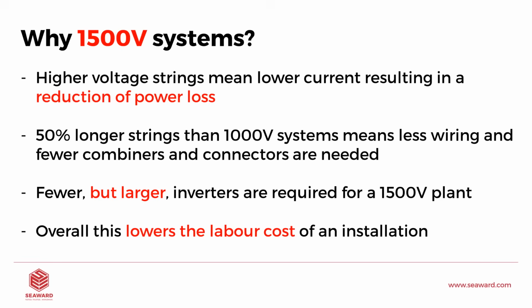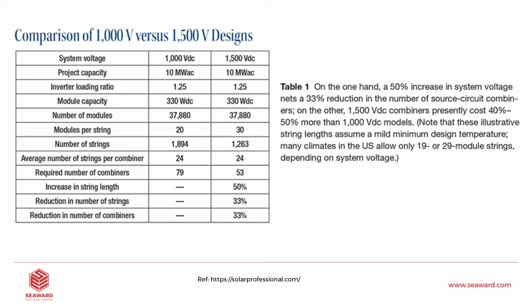And because we have longer strings, we're going to need larger inverters, and that's what's required for a 1500 volt plant. So we actually have fewer inverters, but they're larger, so there is a cost saving there as well. And overall, with lower balance of system materials, fewer inverters, fewer connections, this lowers the labor cost of an installation. So this is the reason we're moving to 1500 volt systems, quite similar to the reason we moved from 600 volt to 1000 volt systems.